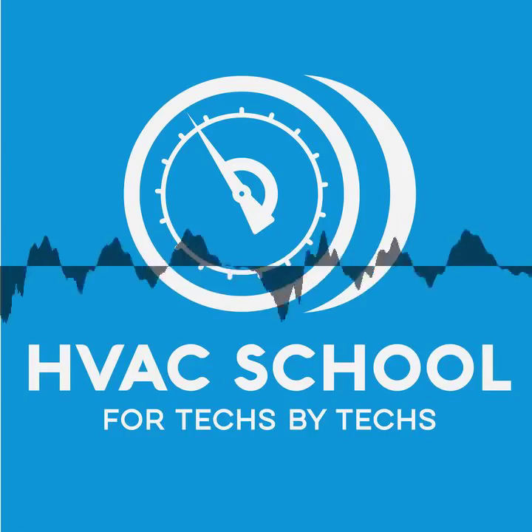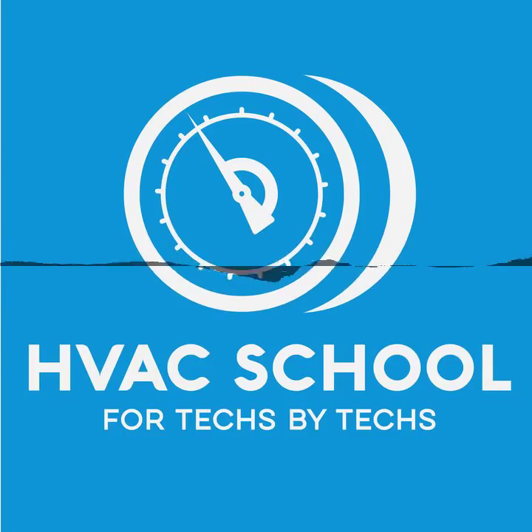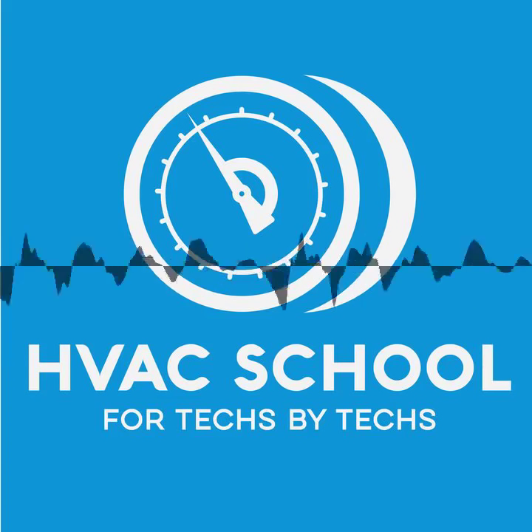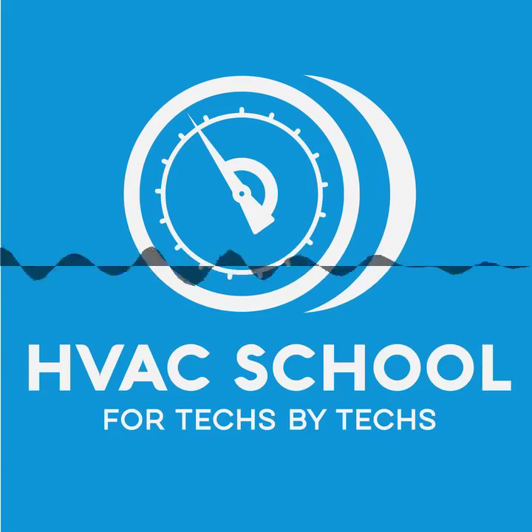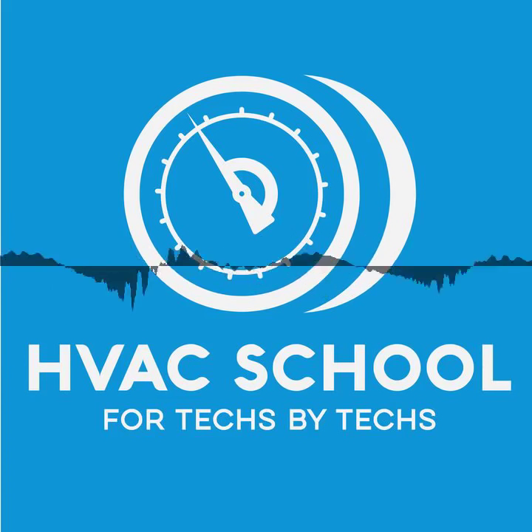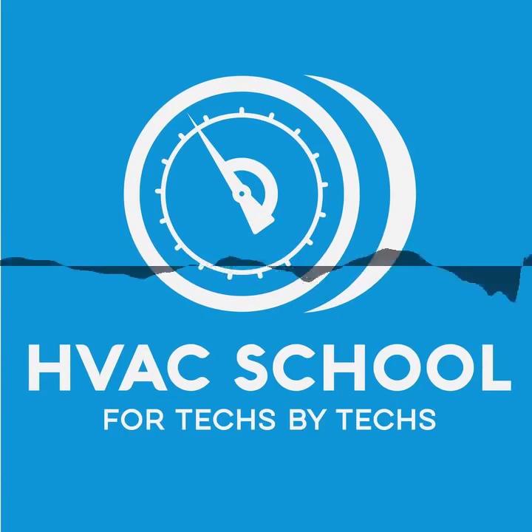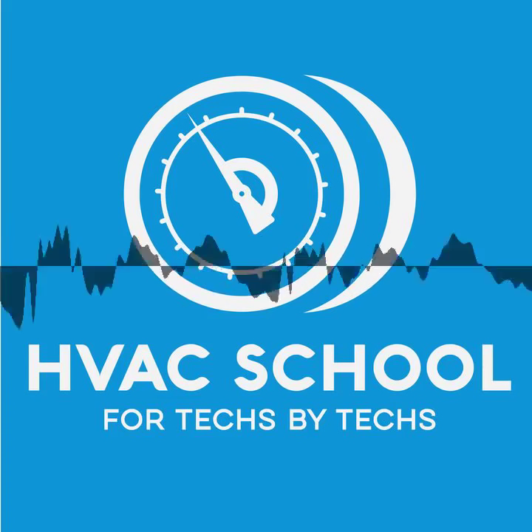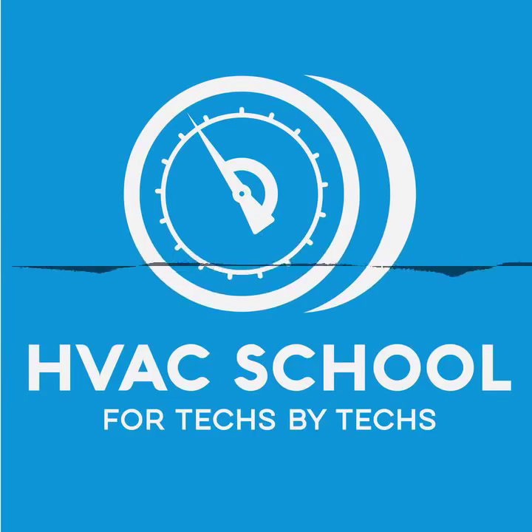All right. Where are you reading 24 volts with the two leads of your meter? Senior techs out there, that's the next question. Anytime someone says they've got voltage, you've got to define what two points they are reading between, because on a voltmeter, you're always reading between two points. You're only going to read voltage across two points that have a difference in charges, and for that there needs to be a reason. Just because they both have potential, meaning voltage in reference to ground or neutral, does not mean there's a difference in charges between the two points you've chosen.